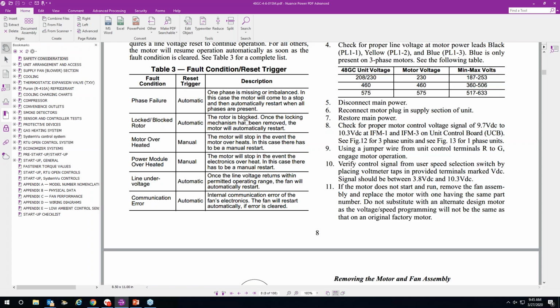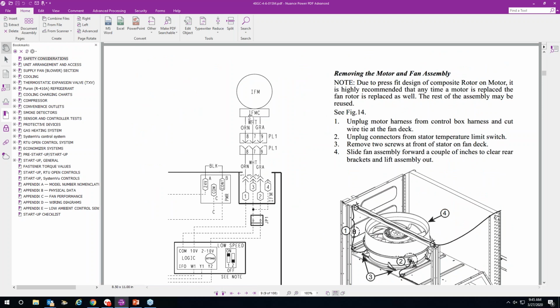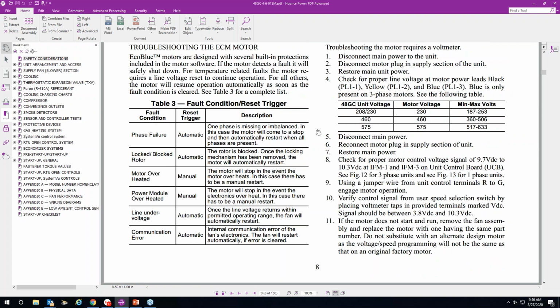If you go L3 to ground, you'll read around 120. If you have that high leg delta, typically it's on the B phase. What we recommend doing is hooking that B phase, that high leg, up to the blue wire on your power supply. So let me get to a schematic somewhere here, and I'll show you what I mean by that.